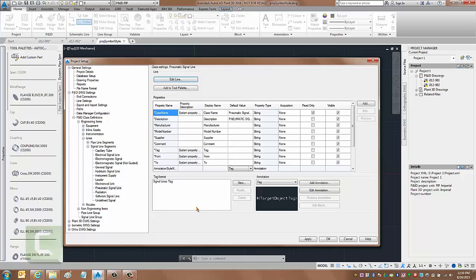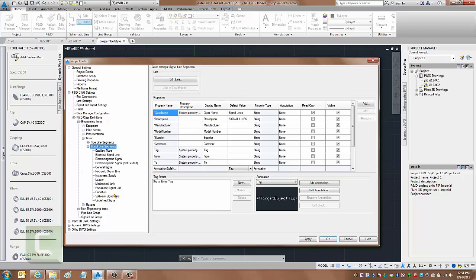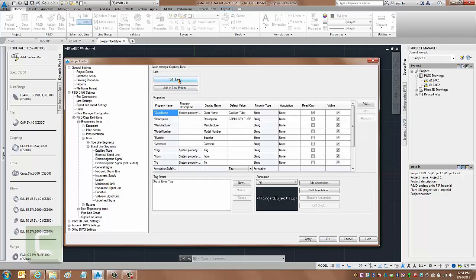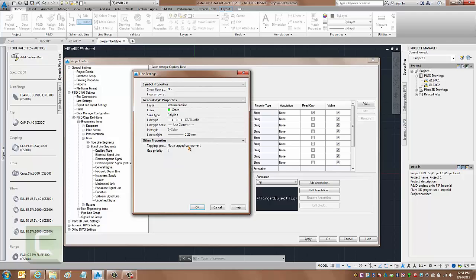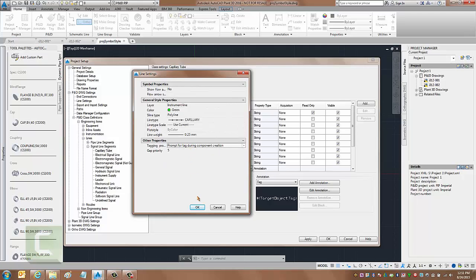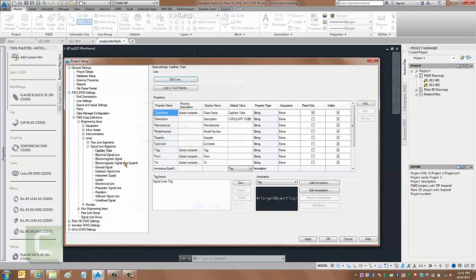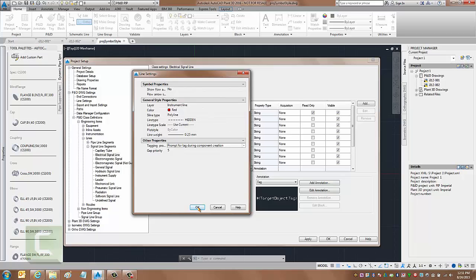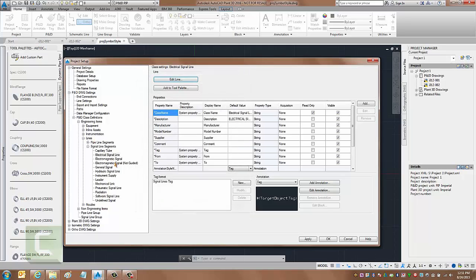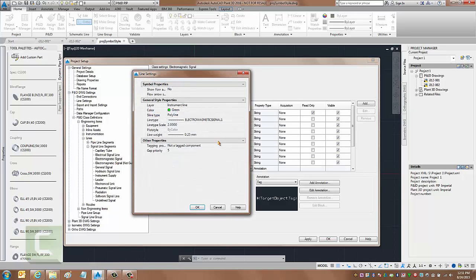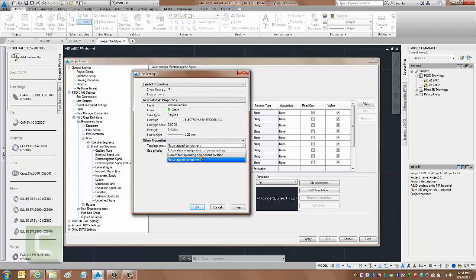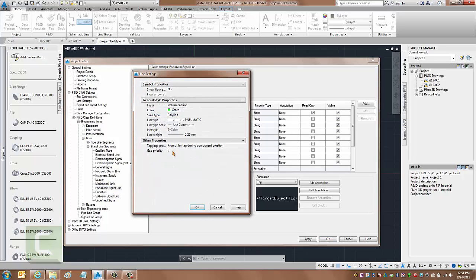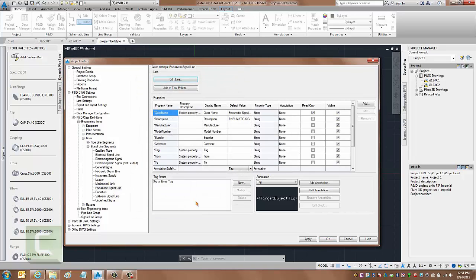Now unfortunately, while I could go to the signal line segments here and change the tag, I cannot just change the line here for everything underneath it. Each one is defined individually. So I'm going to have to go to each one of these lines that I want to be able to tag to be able to use that signal line connector on and make the exact same change. So there's a little bit of work that will take you less than five minutes to do here to just go through each one. Edit the line, prompt for tag, and move on. I'm not going to sit here and make you watch me do all of them here, but make sure I've at least got this pneumatic one done because that's the one I actually have in my drawing.